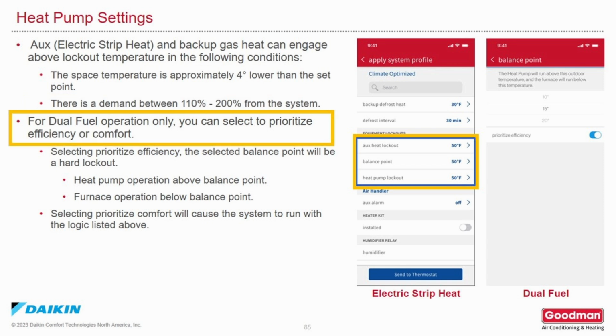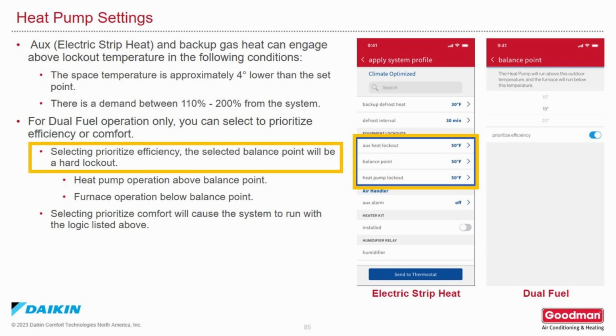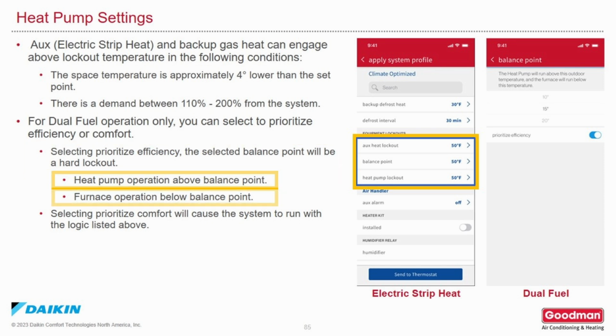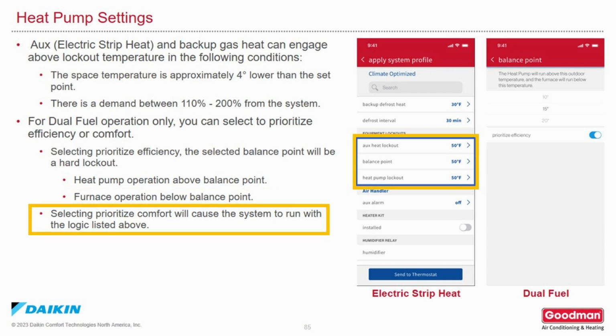For dual fuel operation, you can select to prioritize efficiency or comfort. Selecting to prioritize efficiency, the selected balance point will be a hard lockout: heat pump operation above the balance point, or furnace operation below the balance point. Selecting prioritize comfort will cause the system to run with the logic listed above, such as energizing backup heat at 4 degrees below set point, or for a high demand on the system.